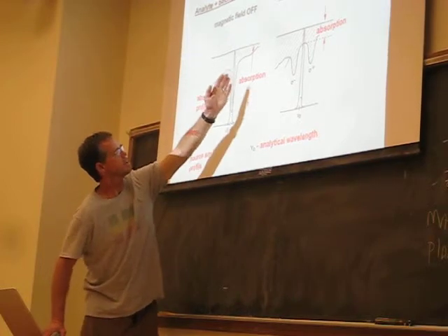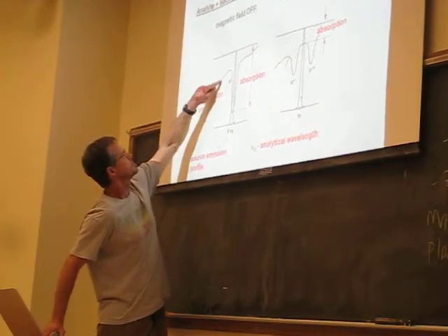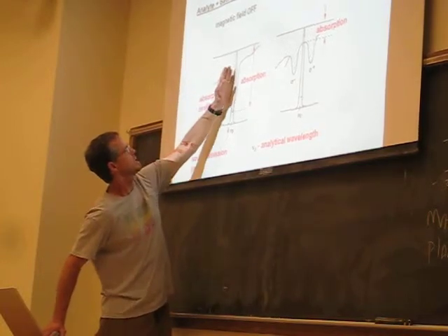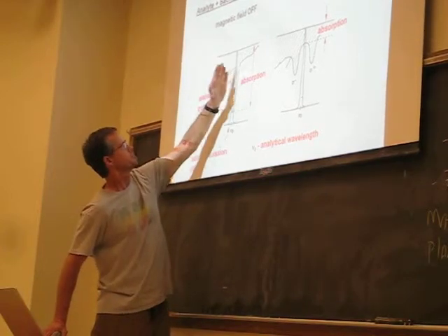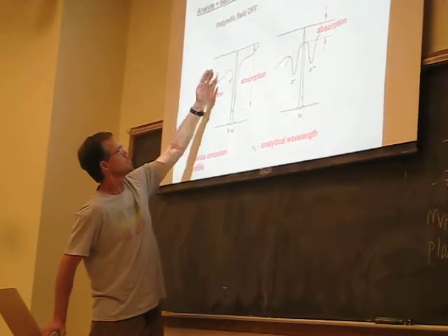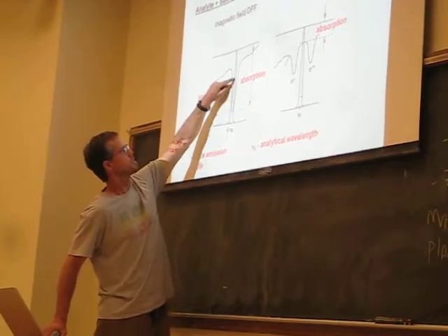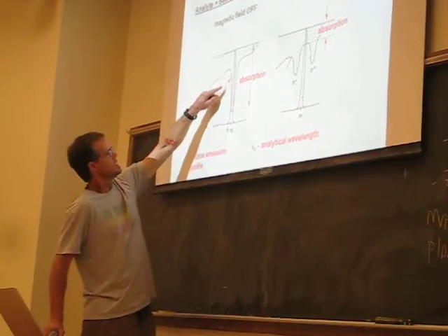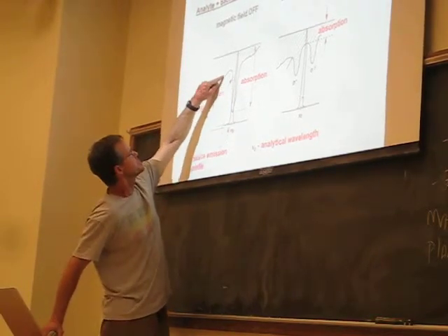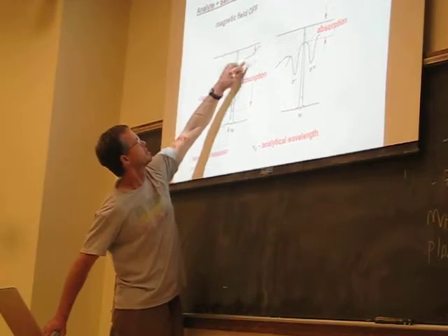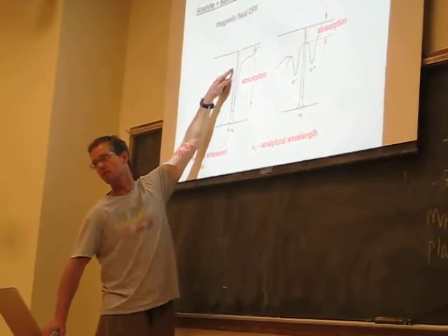This is across wavelengths now, but these are really narrow wavelengths. They're an absorption profile that would have some non-atomic components here, slightly off the main absorption line for copper, which is that. And so this is the background non-atomic absorption. And then we have a much stronger absorption profile that coincides with what's due to copper. And so when we have the magnetic field off, we see both this non-atomic component here, as well as the absorption profile for copper, our analyte.